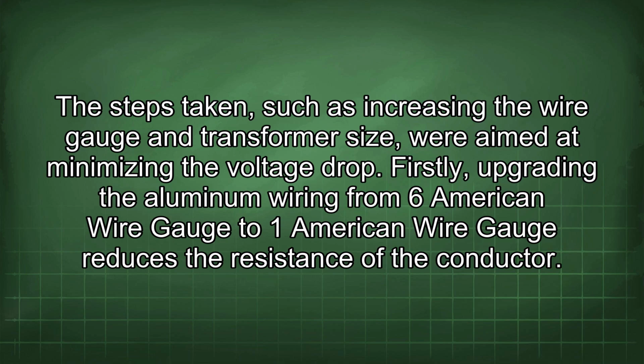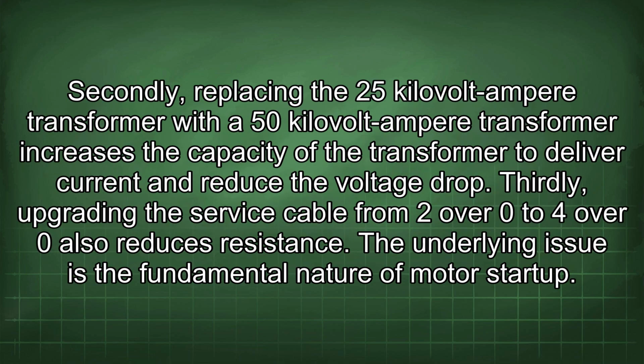Firstly, upgrading the aluminum wiring from 6 American wire gauge to 1 American wire gauge reduces the resistance of the conductor. Secondly, replacing the 25 kVA transformer with a 50 kVA transformer increases the capacity of the transformer to deliver current and reduce the voltage drop. Thirdly, upgrading the service cable from 2/0 to 4/0 also reduces resistance.